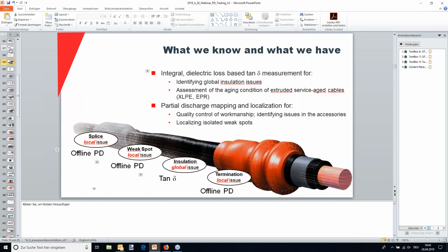You calibrate maybe with 10 nano or 50 nano or 100 nano, so 100,000 picocoulomb, to get a pulse energetic enough that it can reach the far end and come back. At one point, if the cable gets too long, you have to measure from both sides, or you have to cut the cable in the middle and measure both ends.